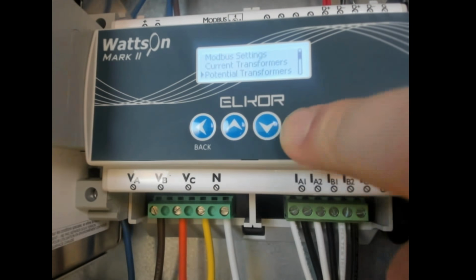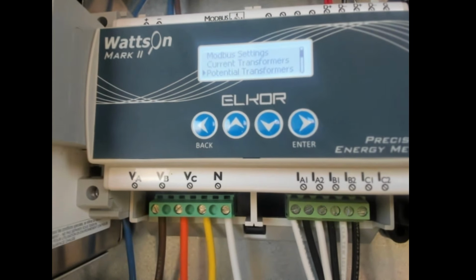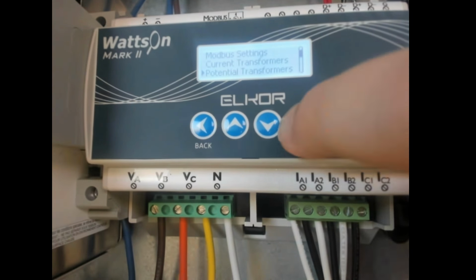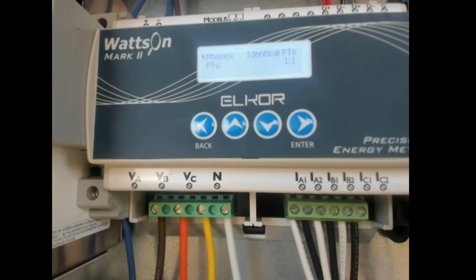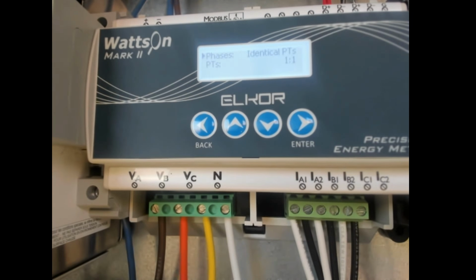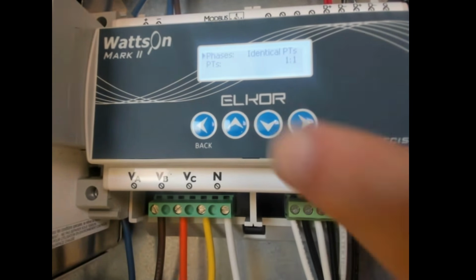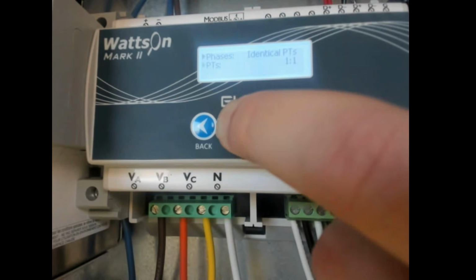The other thing that you might run into, but very infrequently, is potential transformers. Just like a CT is a current transformer that steps down the current from where you're measuring to something that you can actually have the meter look at, the PTs are taking a high voltage and bringing it down to a lower voltage that the meter can actually look at. And PTs, potential transformers, is pretty much what everyone's talking about when they're talking about a transformer anyway. So pretty much there's the PV system, there's a transformer in between just for the meter, and then the meter reads off directly from the transformer. But we need to know the ratio for that transformer.